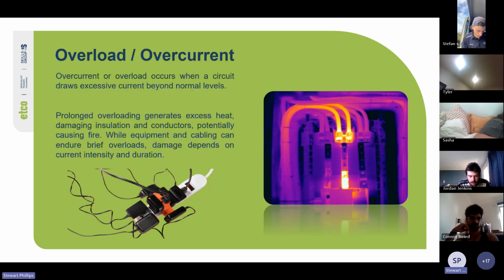So when we talk about overload or overcurrent, it occurs when a circuit draws excessive current beyond normal levels. Prolonged overloading generates excess heat, damaging insulation and conductors, potentially causing fire. While equipment and cabling can endure brief overloads, damage depends on current intensity and duration.